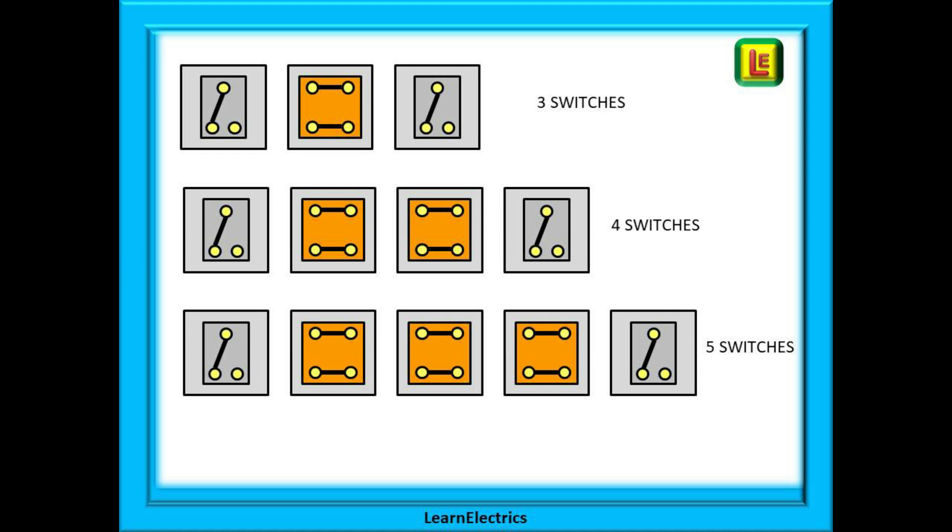The first and last switch must be a two-way switch. All the light switches in between must be intermediate types. And this slide should serve to illustrate that point.